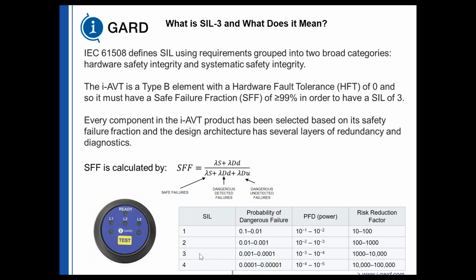For a product to be tested and listed under UL as an absence of voltage tester, you must achieve SIL3, which basically means you're going to have a product which is truly functional and almost guaranteed not to fail in a long time, because this is the type of testing that has to be done on this product. And it took i-Gard a long time to achieve this SIL3 rating because of all the stipulations that had to ensure that the product was not going to fail. And more importantly, if it does fail, it will not fail with an indication of 3 green LEDs, because that will put people in harm's way.